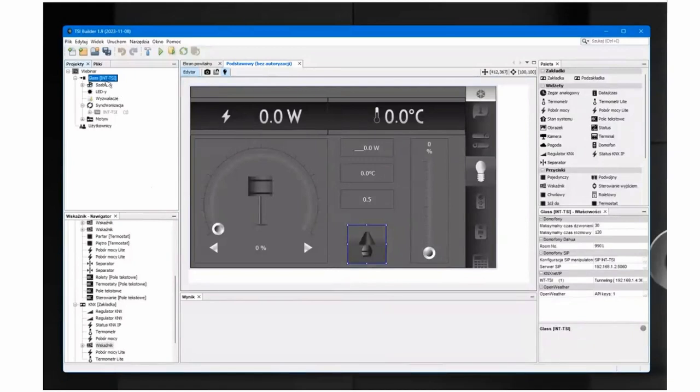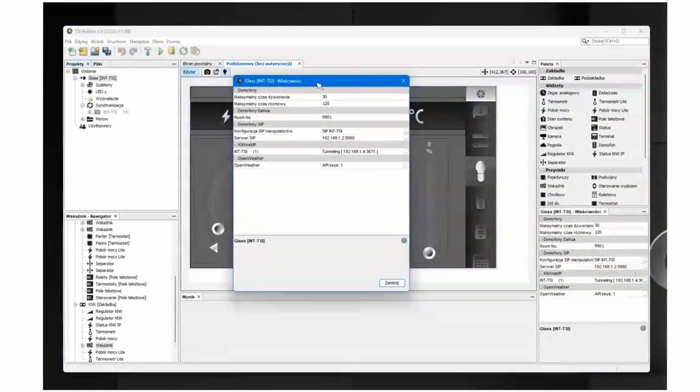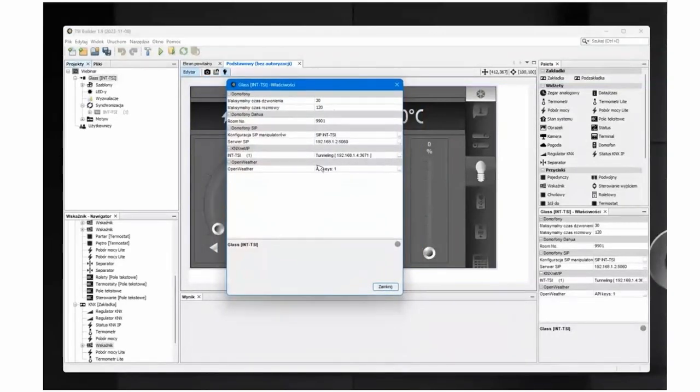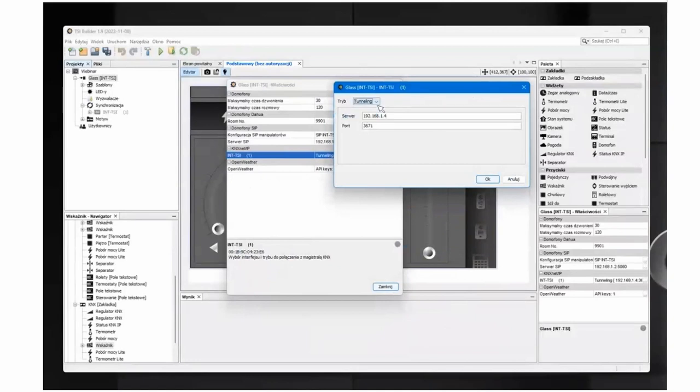After opening target and selecting KNX net IP, choose edit section and select either tunneling for IP and port, or routing. Depending on the KNX device you have in your location, that's the connection that you will be choosing. Also, the program that you need to be using to program and configure the KNX gate is ETS.